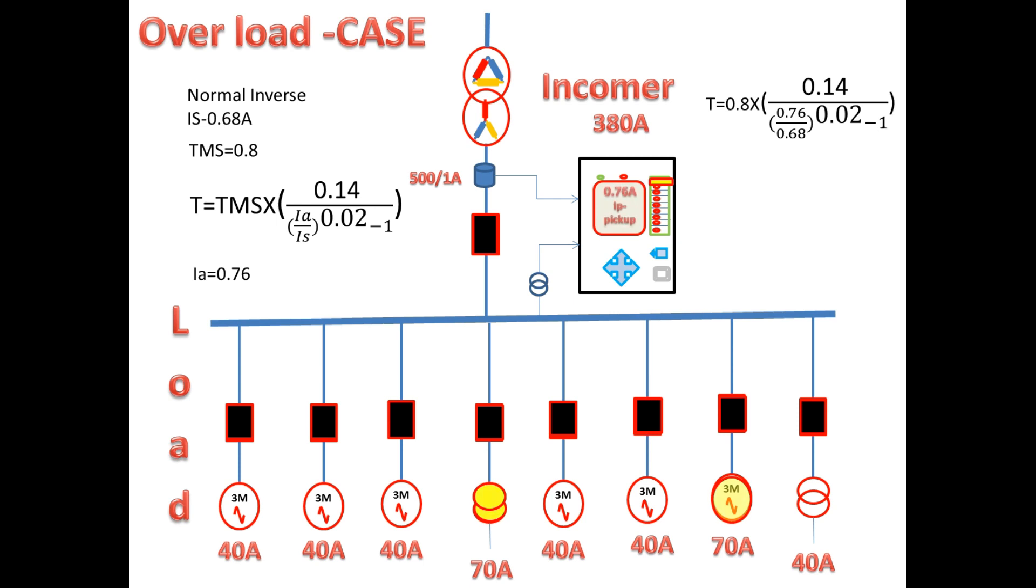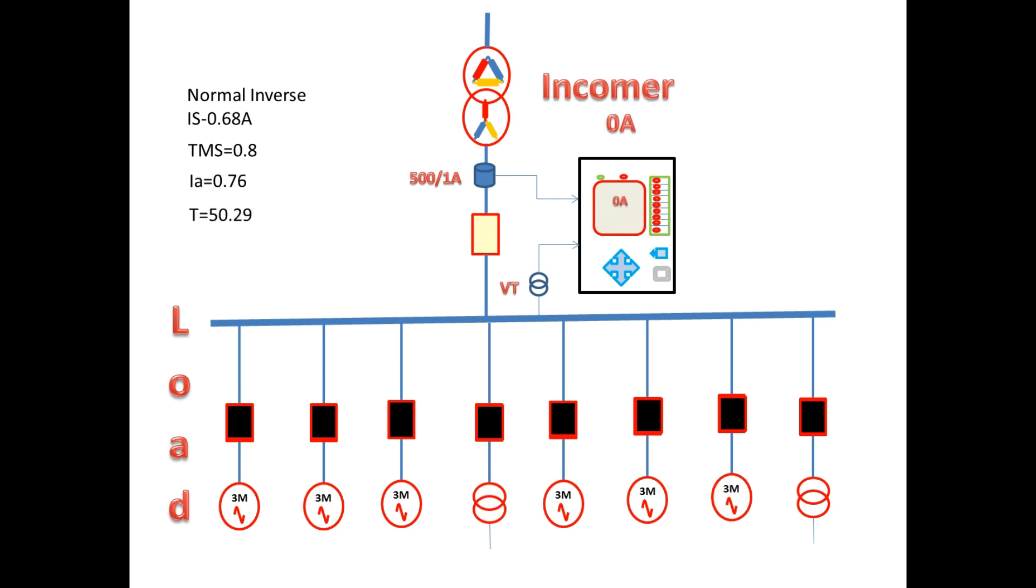So the incomer will wait for 50.29 seconds whether the load is coming back to normal or outgoing CB trips. If still load current is not reduced or these two feeders do not get tripped, then to protect these equipment the incomer has to trip.